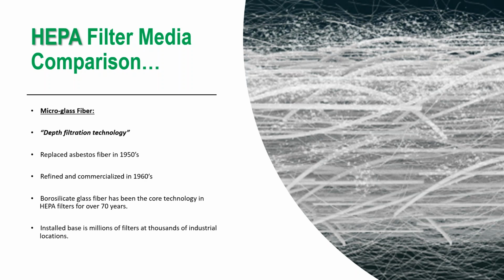Microglass. So that's something that's been around for a very long time. Hopefully everybody on the call has seen a HEPA filter, touched a HEPA filter, maybe even had the opportunity to install one or certify one. So you're very familiar with the monstrosity we're going to talk about. The concept behind glass or microglass filtration is really depth filtration. And the media itself was found, again, as I said, from the Manhattan Project and originally from the nuclear industry.